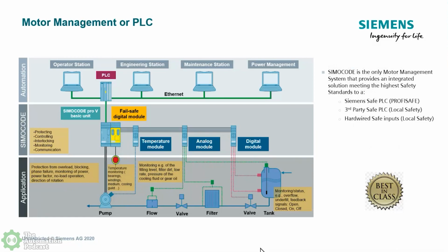I'm able to do that locally and with third-party PLCs, or with a Siemens safety PLC, we can do PROFIsafe, and you have the safety. Now that unit that you see there in yellow is my fail-safe digital module working in conjunction with the SIMOCODE. It's mounted right next to it, and then it opens up the safety that is needed for e-stops, pull ropes, or so forth, whatever is required for your application.